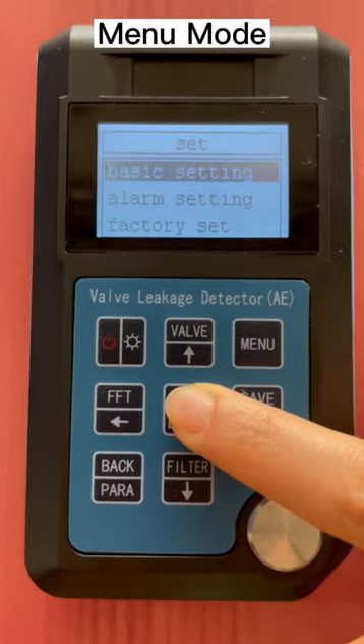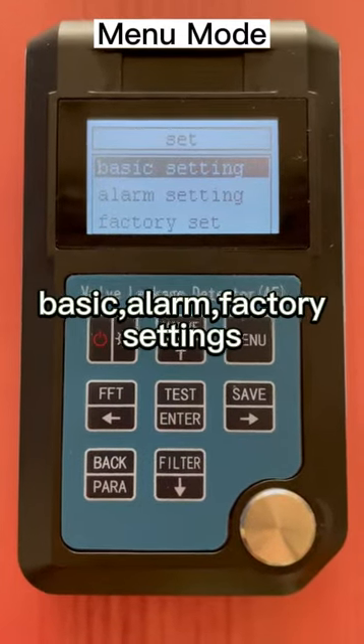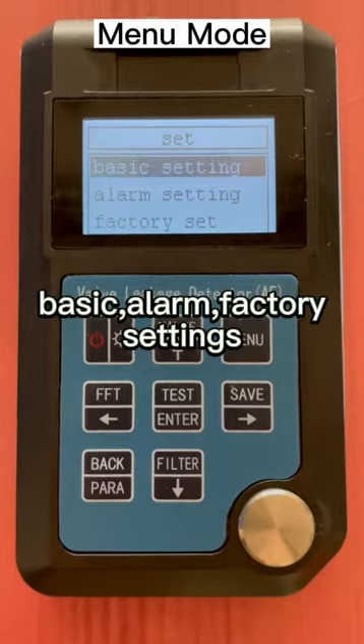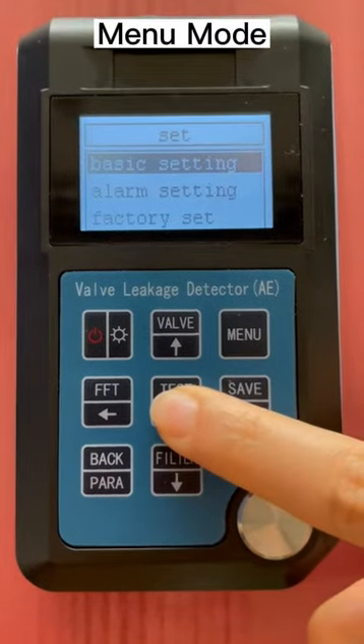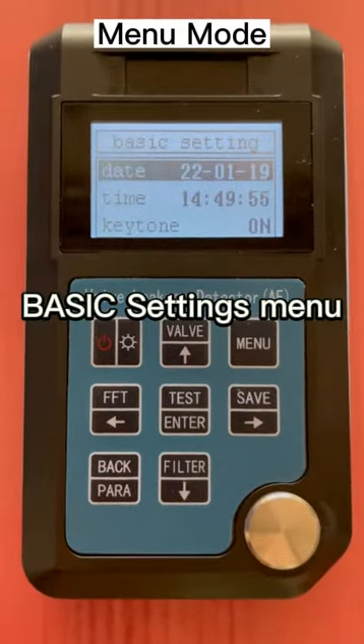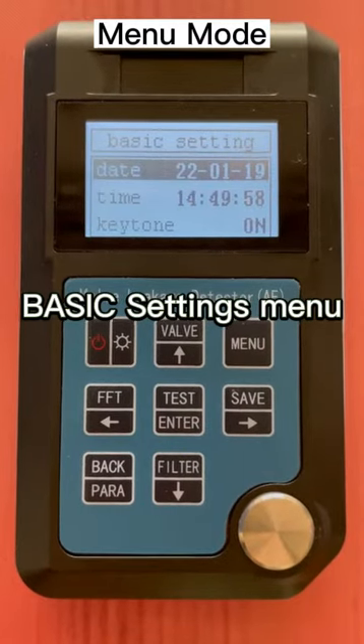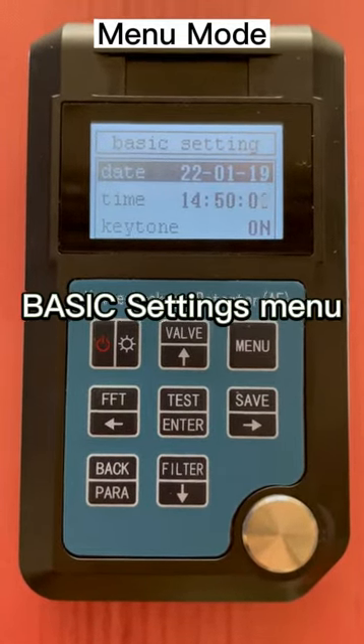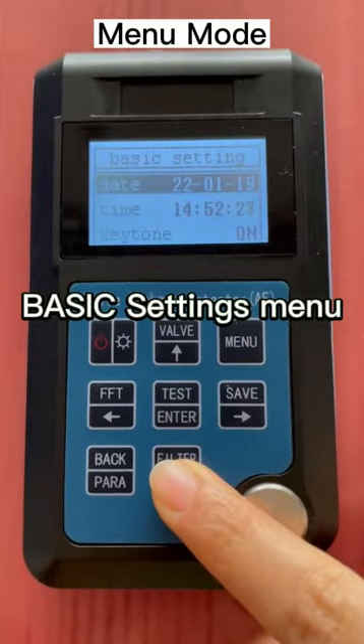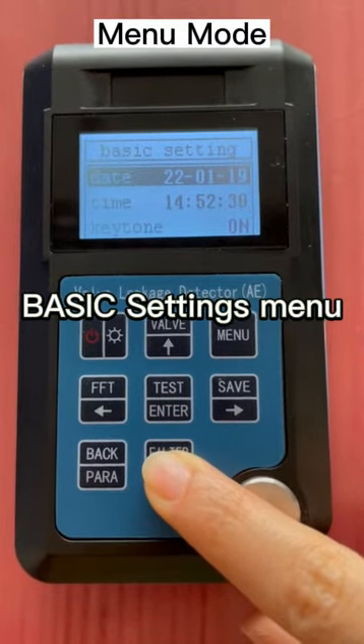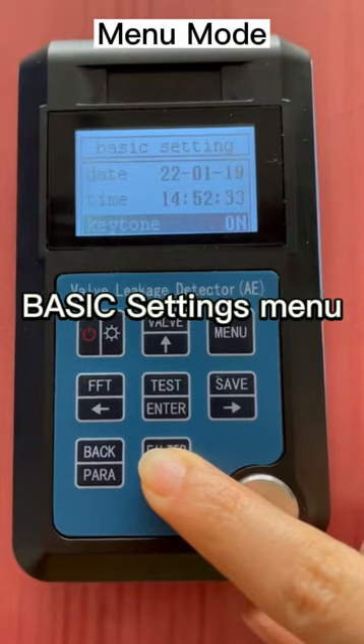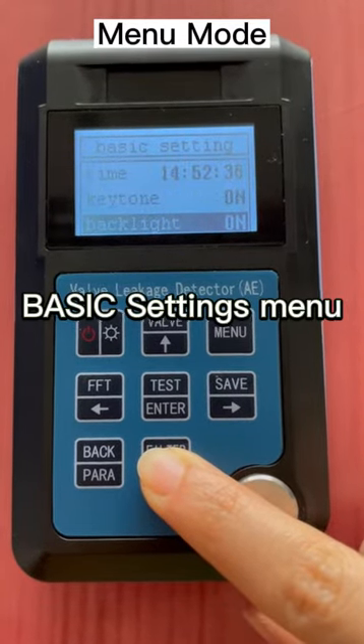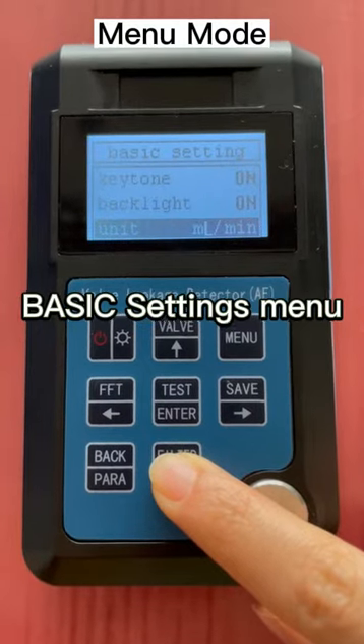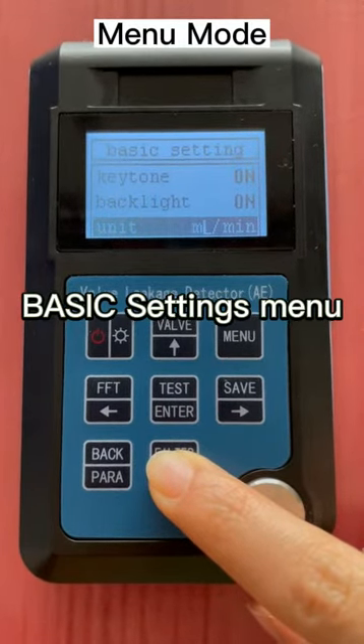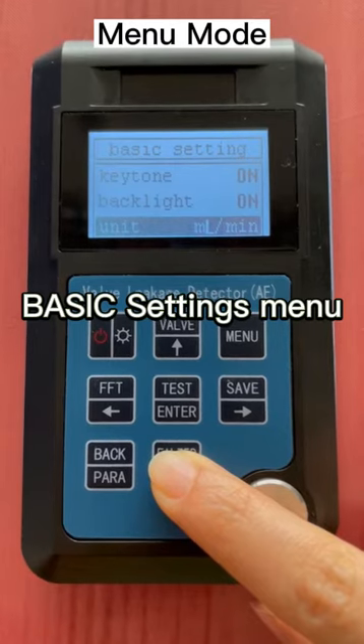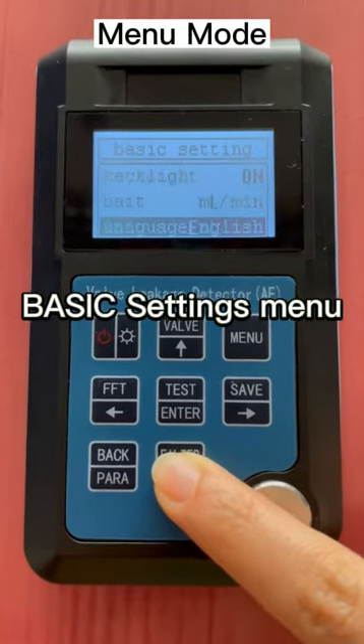The Set menu includes basic settings, alarm settings, and factory settings. In the basic settings, there is some basic information to be checked and modified. Date and time settings will be stored with the measured data. Backlight can be turned on or off. The unit of the leakage reference level can be milliliter per minute or liter per minute.